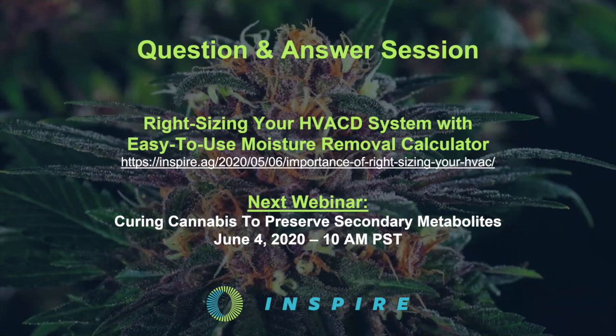Use an epoxy seal. If the rest of the room is sealed, going back to the first part of the question, if the rest of the room is sealed very well and the pressure is controlled appropriately, then outside temperatures and humidities don't actually have that much of an influence. That outside air that's being brought in for ventilation purposes, and we recommend it should be, especially for pressurization and pathogen control and biosecurity, well, that air should be treated.